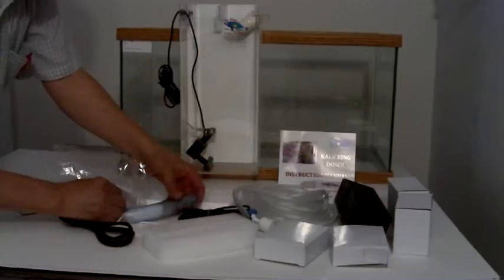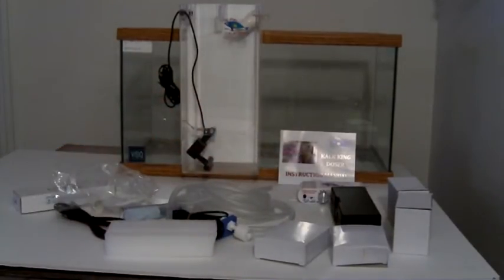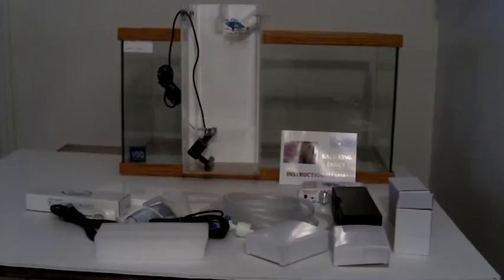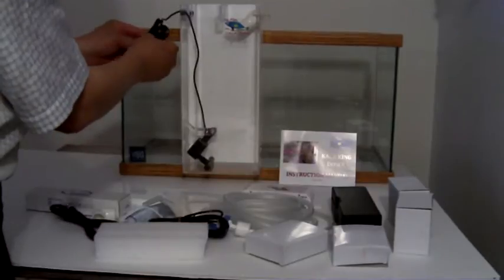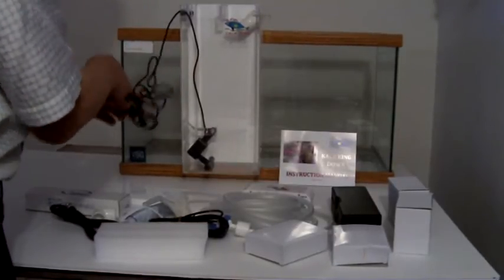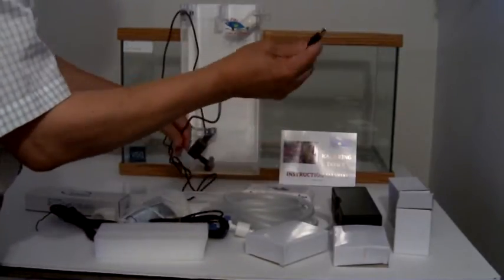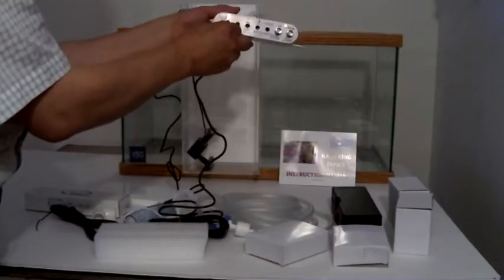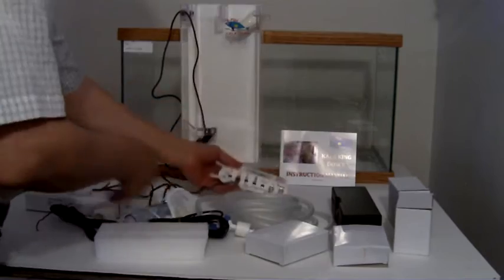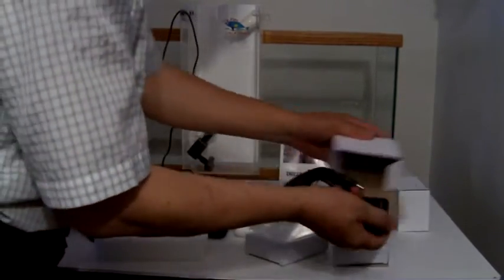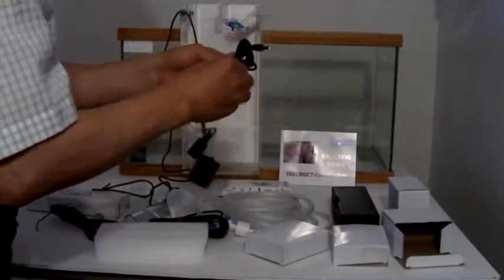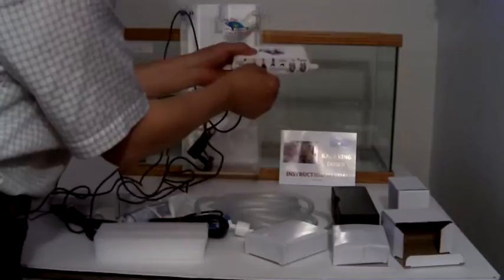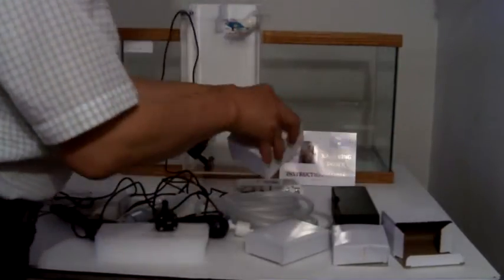And the next thing you're going to do is to set up all the inputs to the computer unit. So over here on the chamber, it already has the stir pump installed, so you don't have to install that. All you have to do is plug this cable into the yellow mixed pump plug, and then go ahead and take out another pump. This one is the red color, which is the feed pump. The feed pump is the pump that feeds the reaction chamber. So you just plug the red to the red, and the last one will be the blue one, which is the bypass pump.